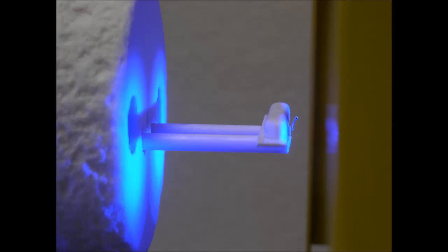If during the sintering process there is a development of liquid glassy phases, which may wet the surface, the sample sticks on the plate, and the sintering process is disturbed. Anyway, if the sample melts on the alumina plate, there is no danger for the dilatometer. This is the main difference between the horizontal and vertical model. The sample of the HT model is set vertical, and it is completely free to sinter.